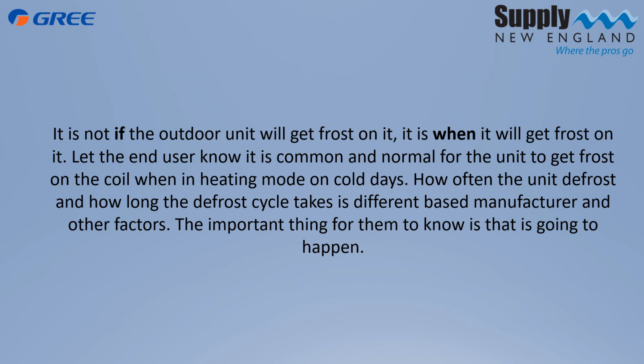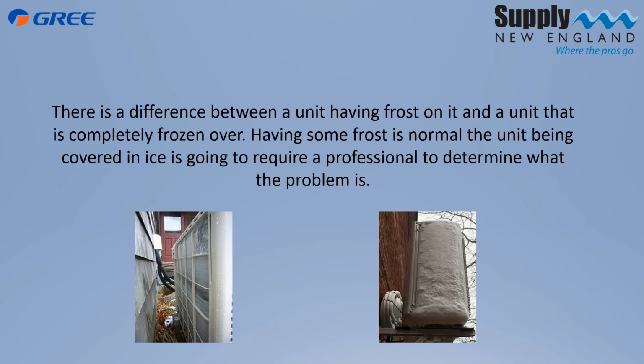And then we need to let them know. It's not a matter of if the unit's going to get ice on it, it's a matter of when it's going to get ice on it. And that's a normal thing to do. They need to know the difference though. If it's a little bit of ice, that's normal. The unit will go through a defrost cycle. Each system defrosts slightly differently, so we're not going to really get into that algorithm. But if they see an ice buildup on it like that, then it's time to call somebody. The professional needs to come out and take a look at what's going on. Traditionally, I find that that's normally a leak in the system somewhere.